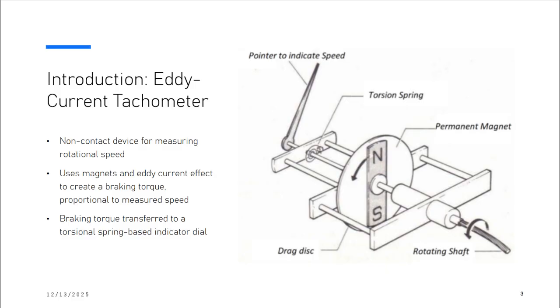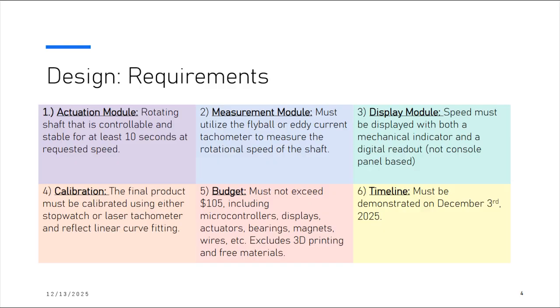As the induced torque causes the disc and its attached pointer to rotate, the pointer will move across the calibrated dial. The faster that the original shaft and magnet spins, the stronger the induced eddy currents and the greater their magnetic force, and thus the more the pointer deflects. Eventually, the system will reach an equilibrium point where the electromagnetic torque generated by the eddy currents is perfectly balanced by the mechanical resistance of the spiral spring. The position of the pointer at this equilibrium directly corresponds to the rotational speed of the shaft, which then is read in RPMs.